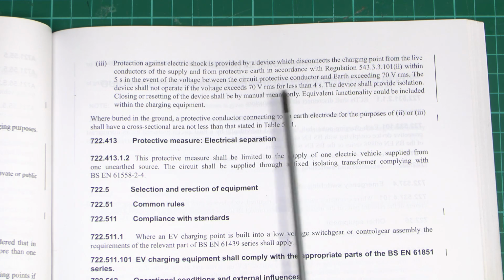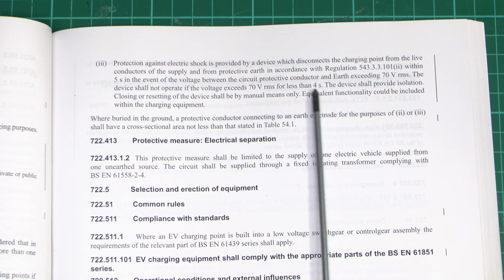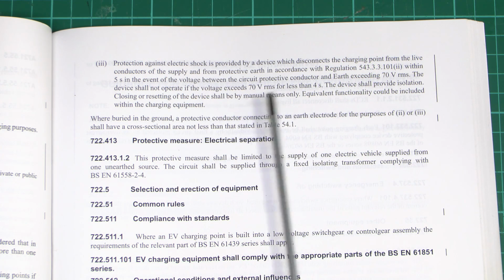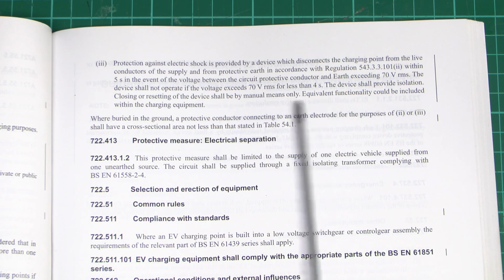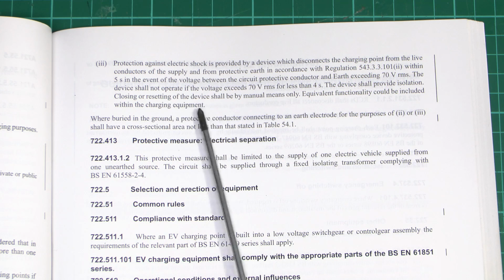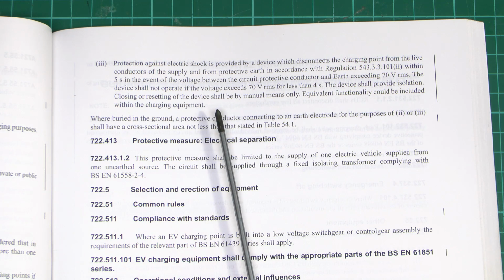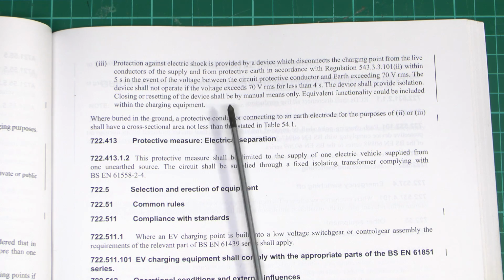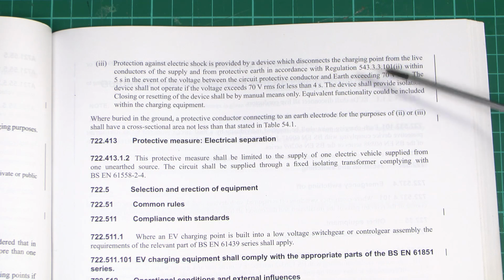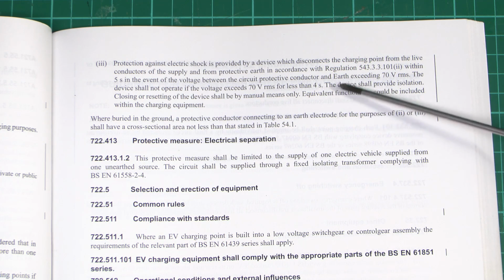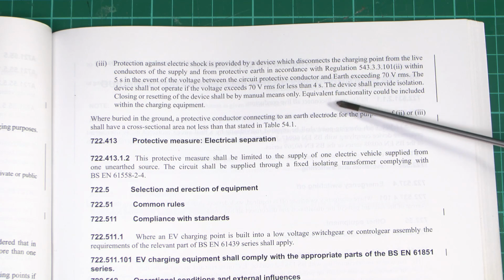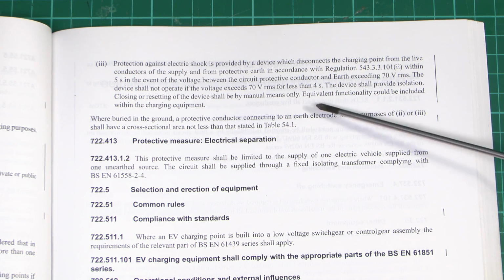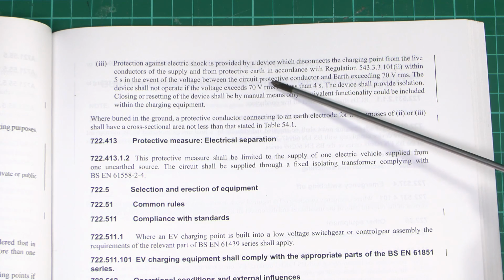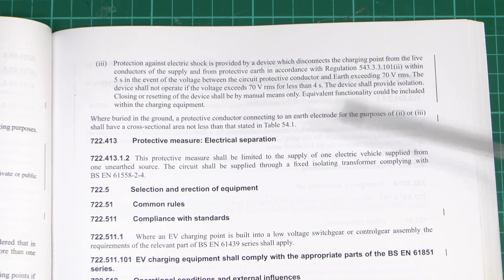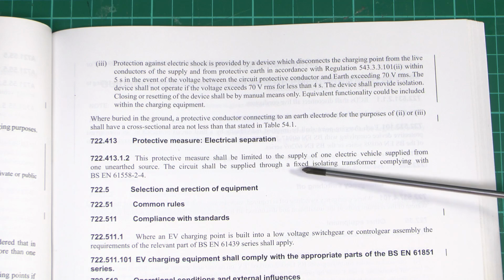Now, at the time of making this video, which is in November 2018, these devices don't actually exist. And although it states here that it could be included within the charging equipment, certainly at the moment that's not an item that exists. Of course, it may do in the future. This is effectively similar to the old voltage operated earth leakage circuit breakers which went out in the early 1980s. The only difference here is that this will disconnect the protective conductor as well as the other two, meaning the whole thing is totally disconnected.